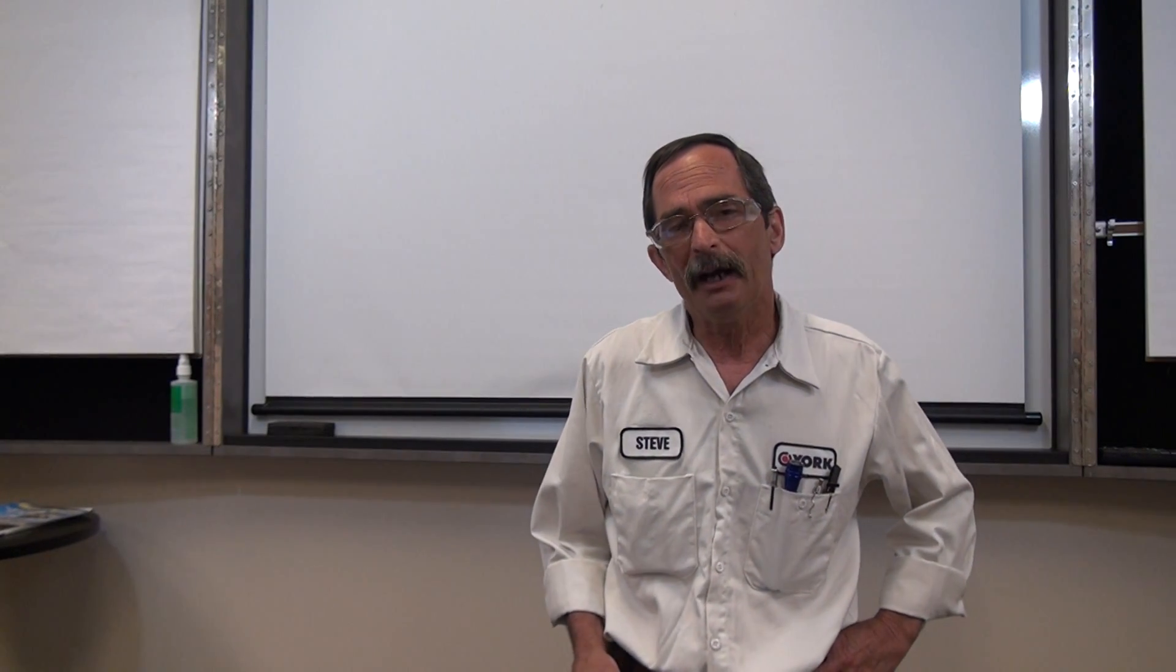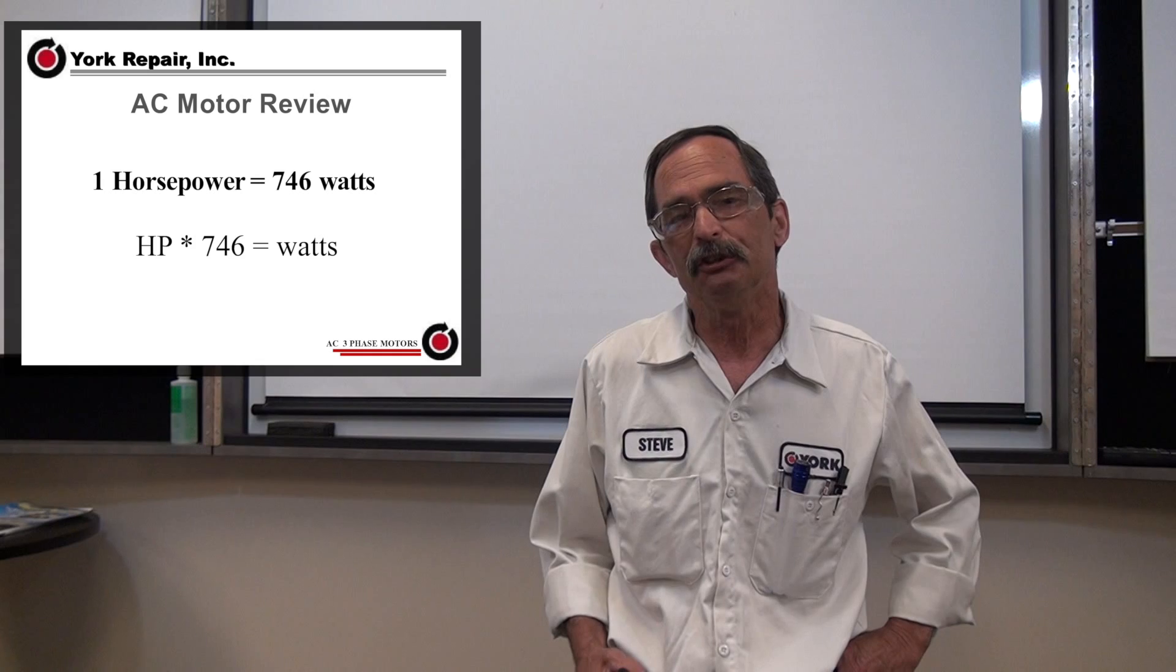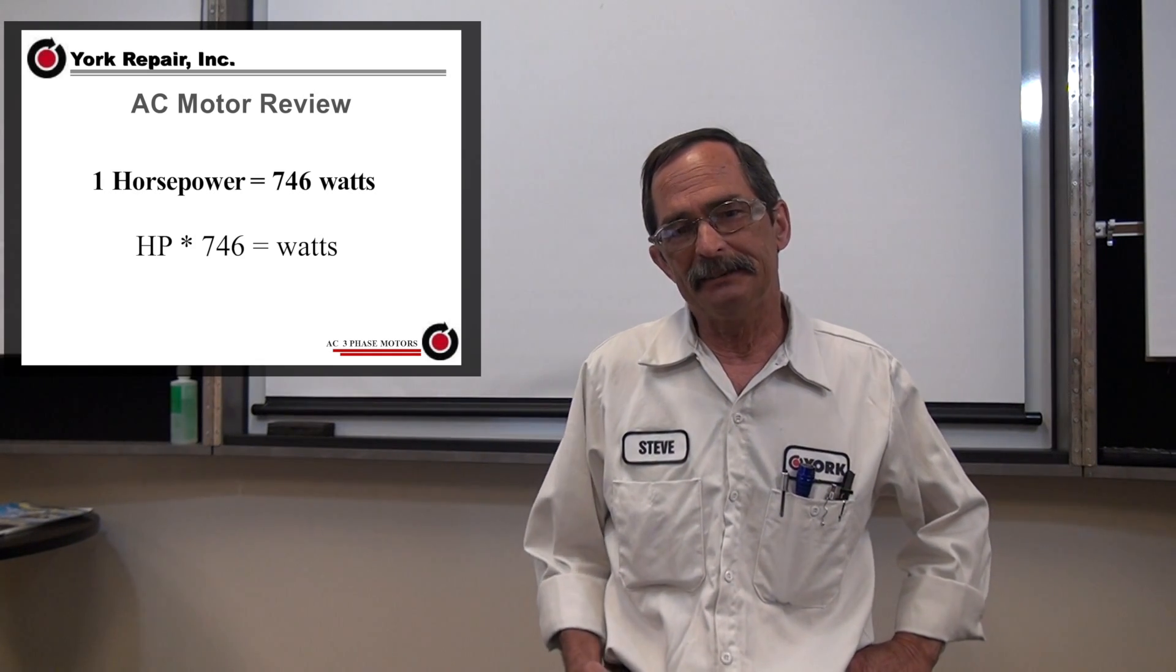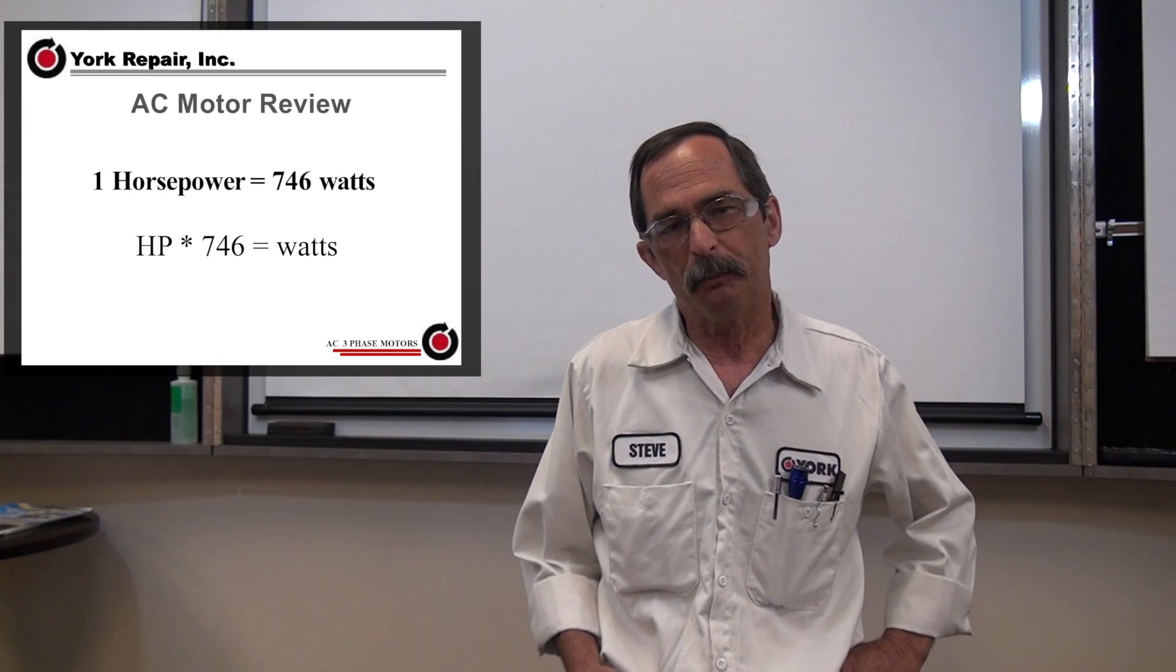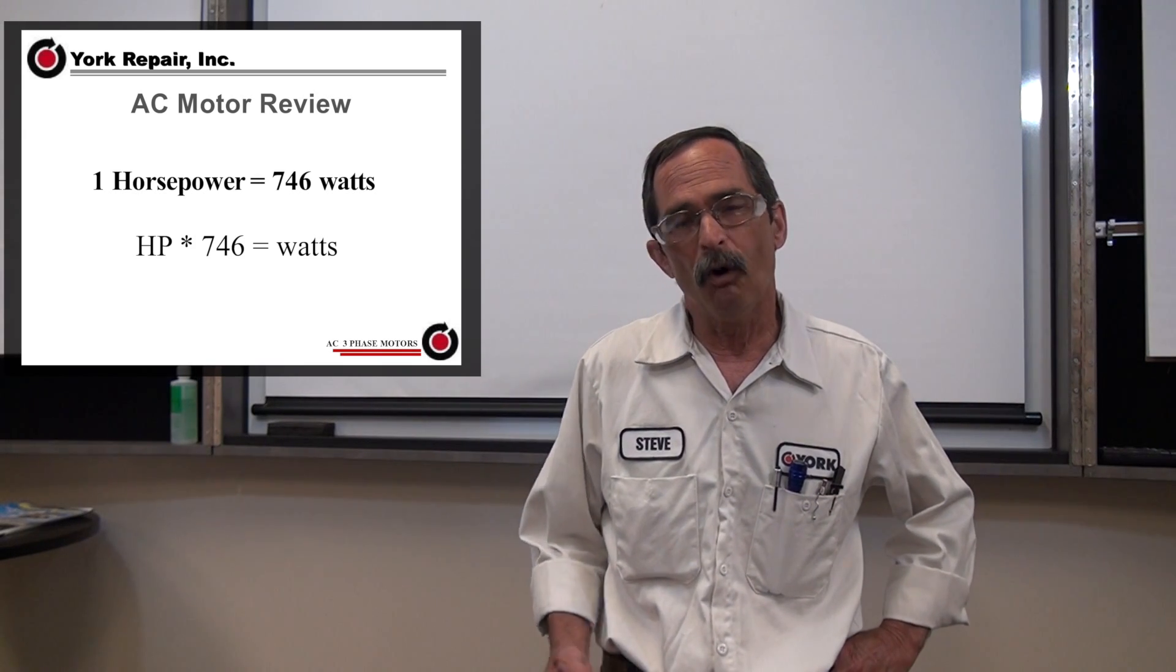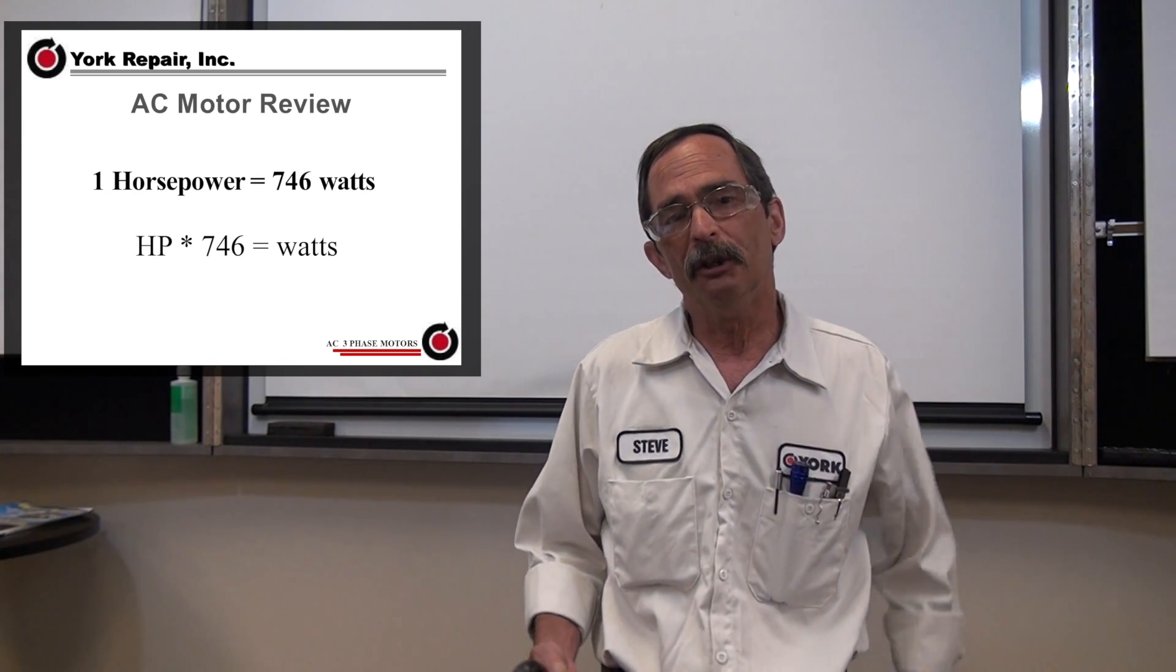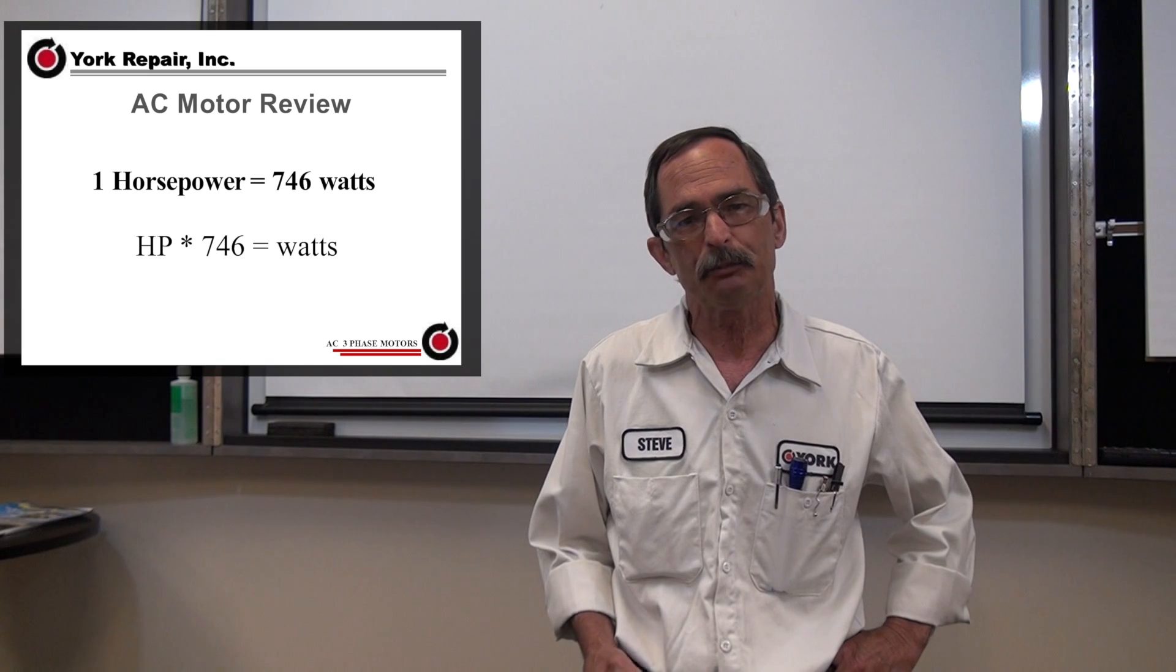The other thing that's very critical on a motor nameplate is the new IEC motors. The international standards, which are metric, are all in kilowatts. In the United States we're used to using horsepower. In the IEC they use kilowatts. There's 746 watts per horsepower, which is very important. So if we're looking at a motor that's got 1.5 kW, we know we're looking at a 2 horsepower motor.